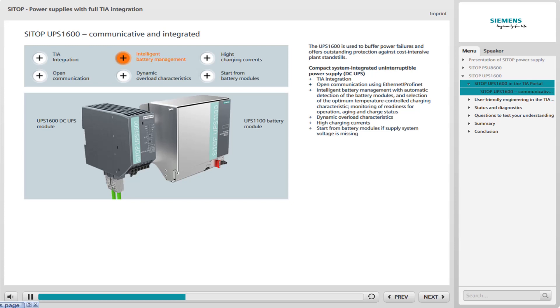Battery management is one of the most important tasks. The UPS 1600 automatically detects the connected battery modules via the energy storage link and charges them with the optimum temperature-controlled charging characteristic. Intelligent battery management monitors all the relevant data, also in the case of battery modules connected in parallel.